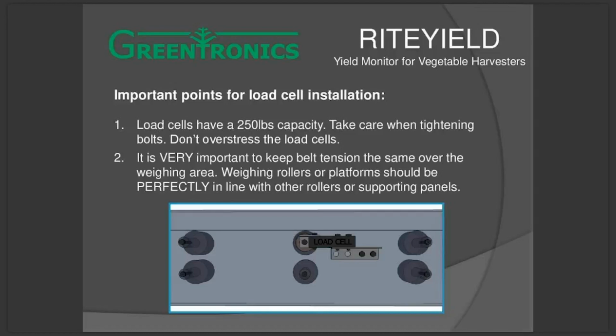You don't go over the capacity and overstress them, because then they're no good and you have to buy a new one. The belt tension is a very important part to think about. So the load cell roller needs to be perfectly in line with the rollers before and after. Because if it isn't, then you're changing the belt tension, and then the belt tension itself becomes a component of how we see weight. And you don't want that, because that makes the system less accurate. So it's important to take a straight edge or level and make sure that you've got things lined up right when you do the installation.